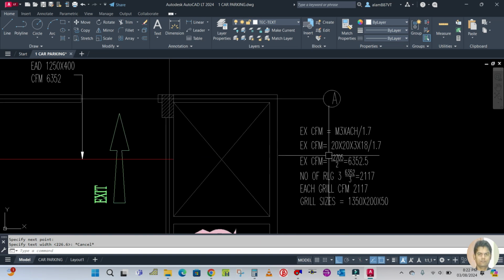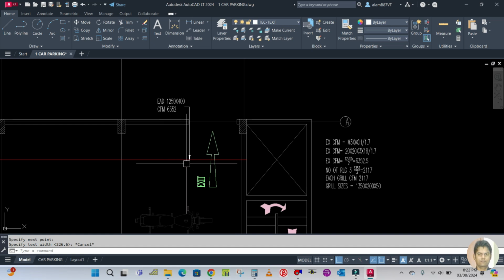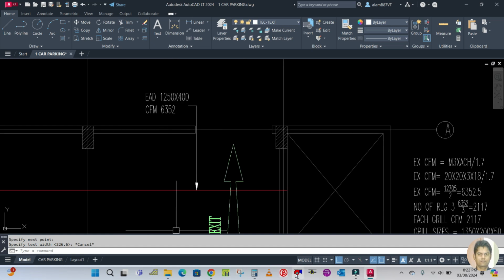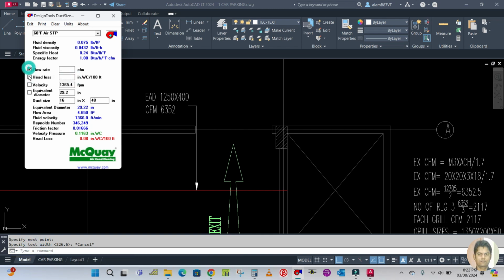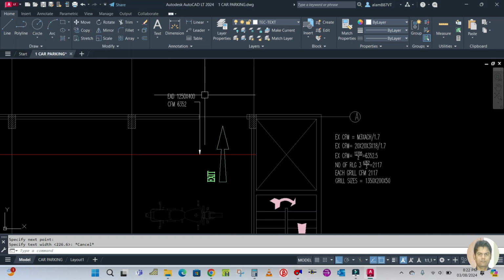the total CFM here is 6352. So how to do the designing here, you can see 6352, and select this flow rate and head loss. Okay, enter the flow rate 6352 and head loss is 0.08. And now go to this unit and select the metric system and enter the height of the duct. So I'm going to enter 400, so I will get it here 1250.